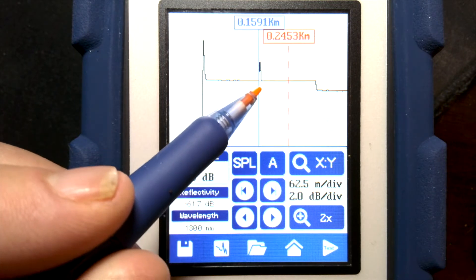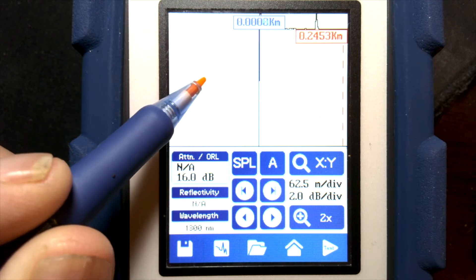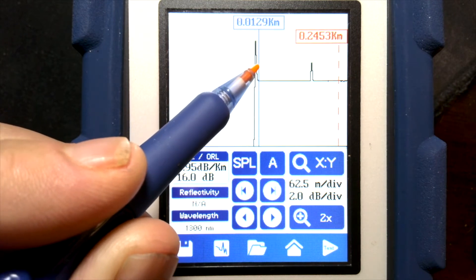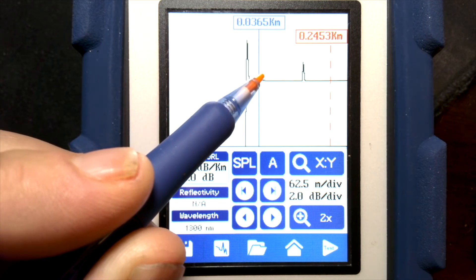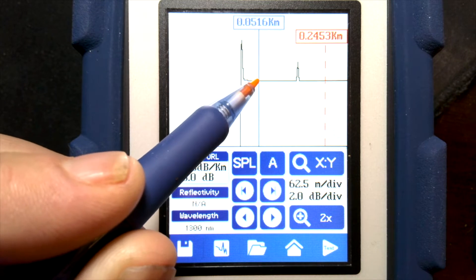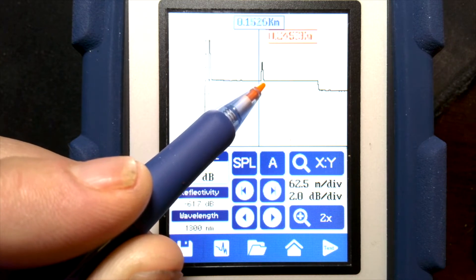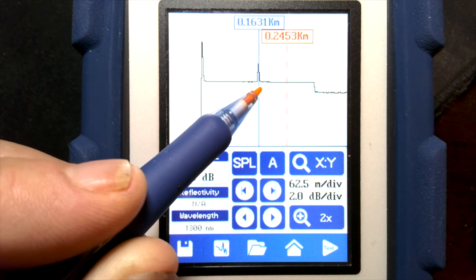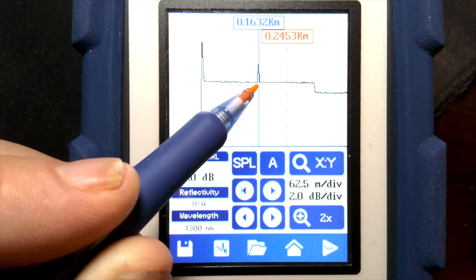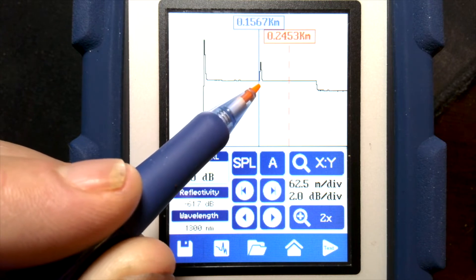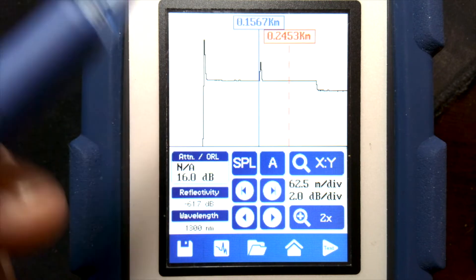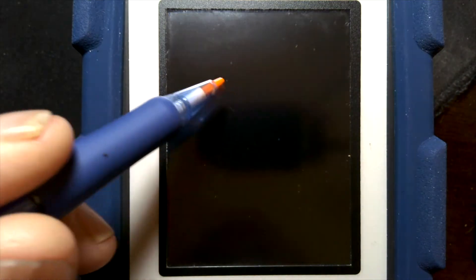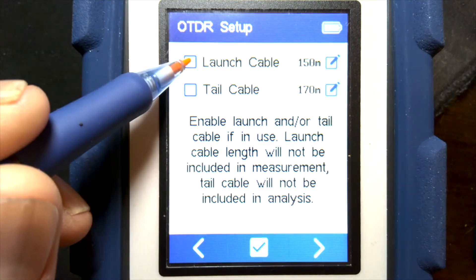Our reference for zero is down at the beginning of the fiber, so we're including this section of fiber in our distance measurement as well as the loss of this section of fiber, and we're measuring the loss of this first connector. Let's go back and reshoot this trace with the launch cable setting turned on.